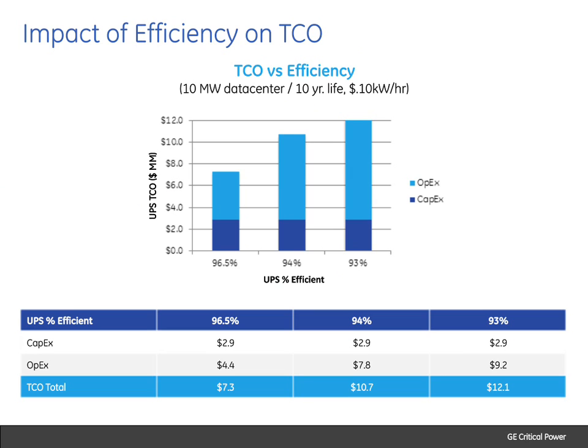If we applied that to a 10-megawatt data center with a 10-year life, 10 cents a kilowatt hour, and assume the UPSs are at 50% load, you can see the difference. We've looked at CapEx and energy costs, and you can see the difference it makes going from 93% to 94% to 96.5% efficiency. There are different types of UPSs and topologies that will give you different efficiencies, and some operating modes could get up to 99% and save even more.